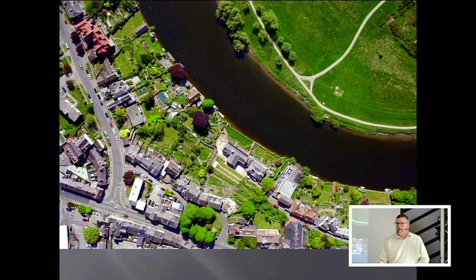There are screens in there to prevent elvers and other fine things as well. You might think, why is it built there and the pumping station's there? It's because the natural flow of a river, as it comes round a bend, the outer bend is actually faster flow. So we're hoping the leaves, litter, and other debris get swept round that way. The only thing that does build up, of course, the heavier stuff, silt and sand and clay, will start to develop there. So we do have a problem every few years where we have to clean the front of the intake just to get it back down to that level so we can gravitate out the river and get enough water coming across.